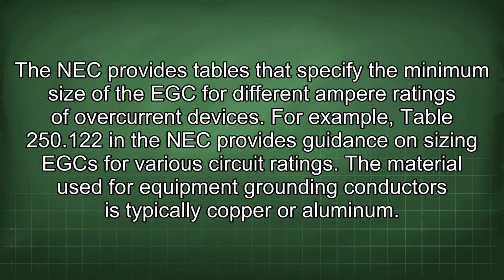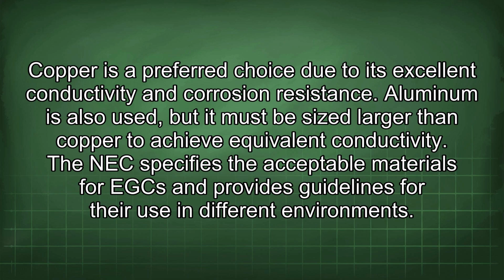The material used for equipment grounding conductors is typically copper or aluminum. Copper is a preferred choice due to its excellent conductivity and corrosion resistance. Aluminum is also used, but it must be sized larger than copper to achieve equivalent conductivity. The NEC specifies the acceptable materials for EGC and provides guidelines for their use in different environments.